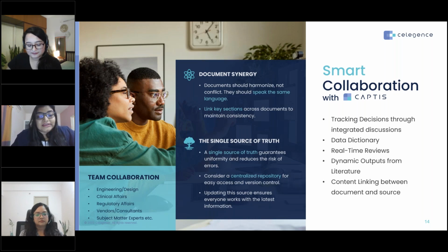But this was not reflected across all the documents. So we have the notified body reviewer looking at a recent PMCF plan that says it's a biannual activity, but they have a clinical evaluation report that calls it an annual activity. So it's about where data is coming from, and essentially we need to have correctness and consistency of information to ensure that we have the right safety and performance information for the device.